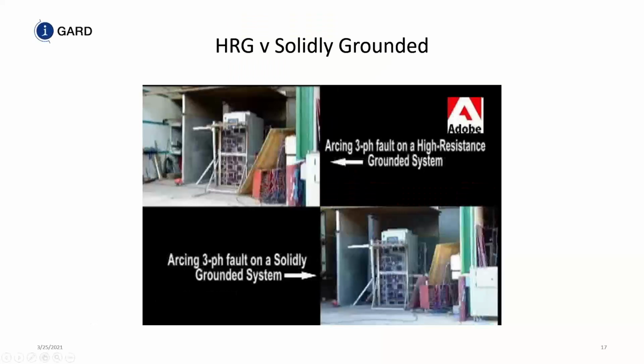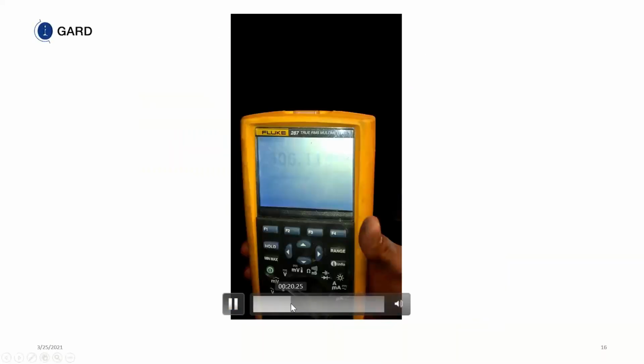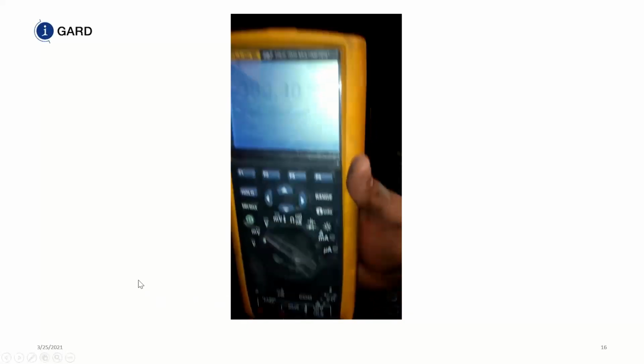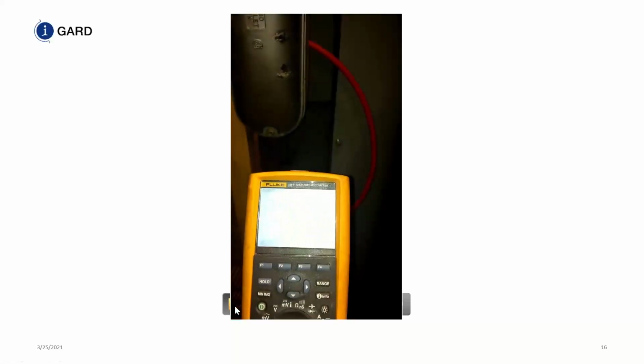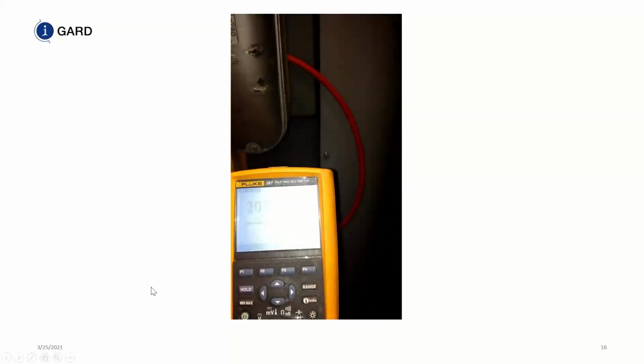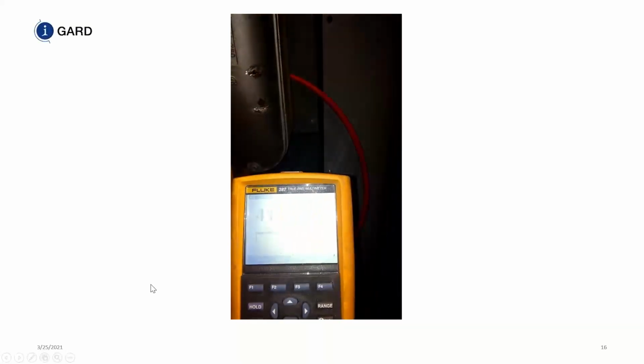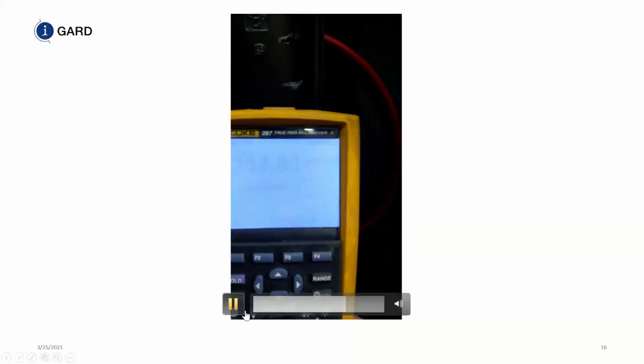You've heard the expression that current takes the path of least resistance. Oh, I apologize. Current takes every single path that's available to it. So if you take a look, I'm right around an elbow over here. So I can actually determine that the fault is downstream from this location, even though I didn't have to open up any doors and place my employees in harm's way to find where that fault is. So I can go around bus duct and tell you exactly which drop has the ground fault. And so you can find the fault very, very quickly with this type of system.